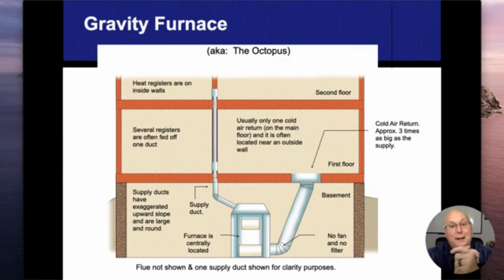And they're old. I don't know what much more to say. These are typically going to be in houses that were built before World War II. I don't think we were really using these things after World War II, but there is a possibility. But most of them are going to be in homes before World War II. No blower fans, no filters, slow air movement. Principle that hot air rises, cold air falls, creating a convection loop. So the hot air would come up here, and we'll leave through this room here, and then cold air would come back down, get reheated, and basically we're creating a convection loop inside here for a gravity furnace.